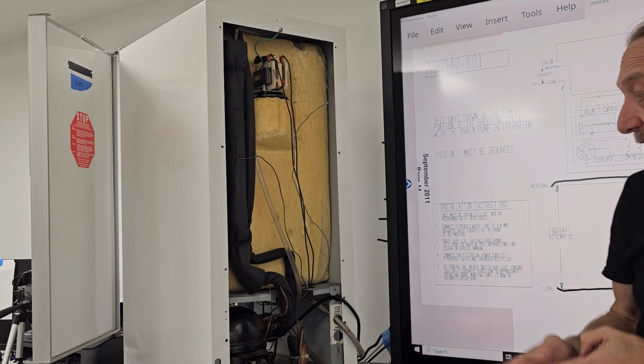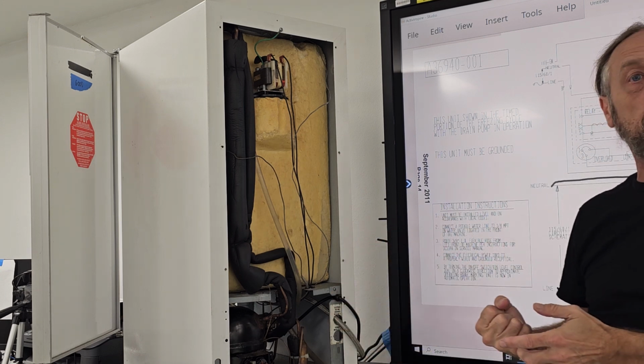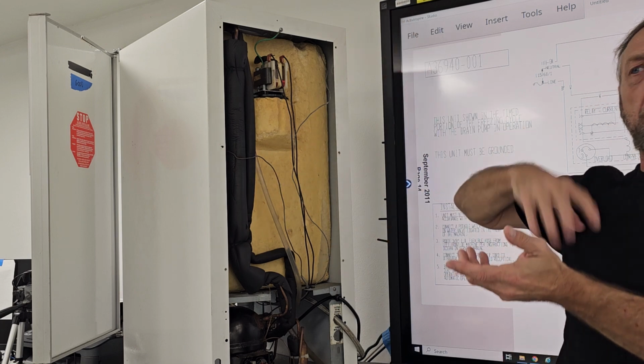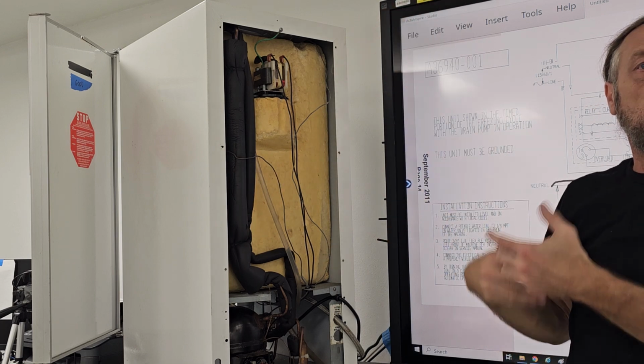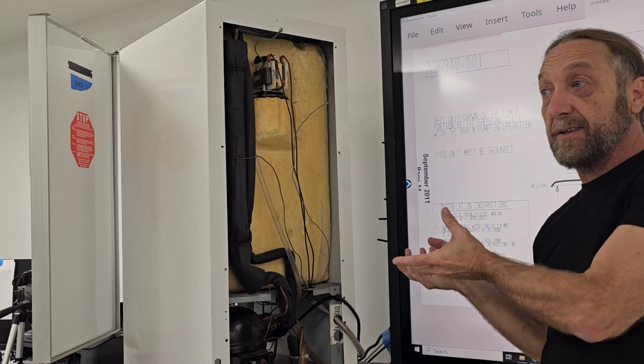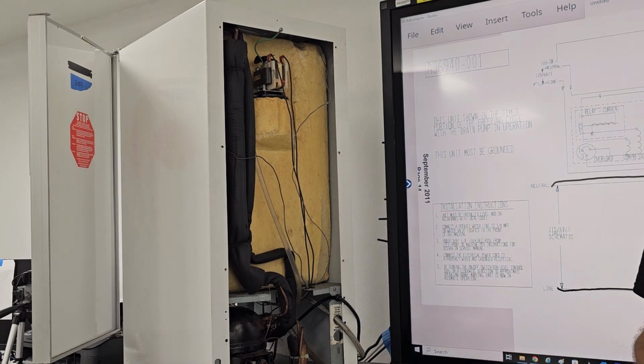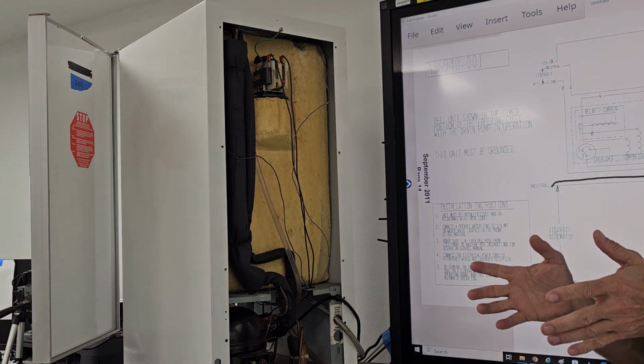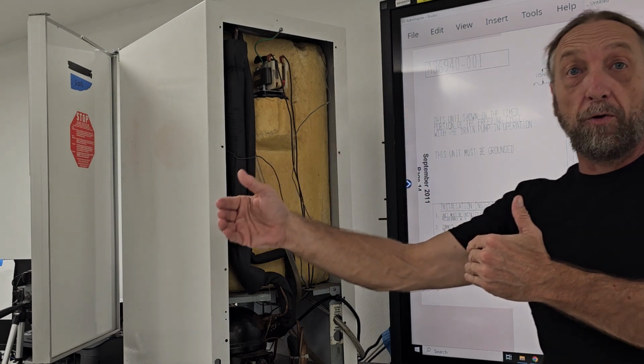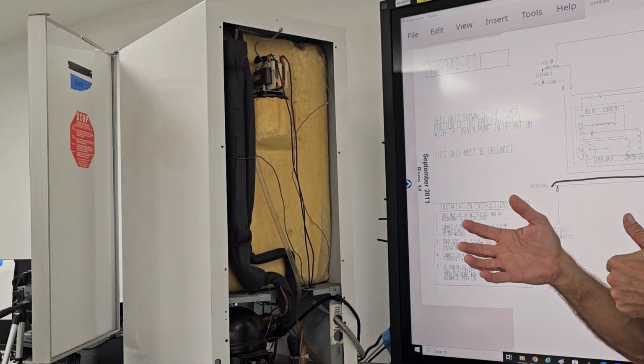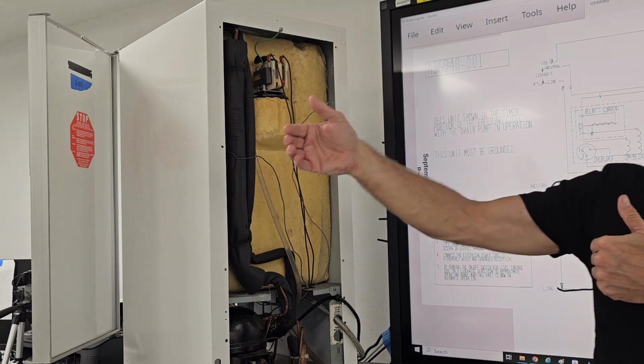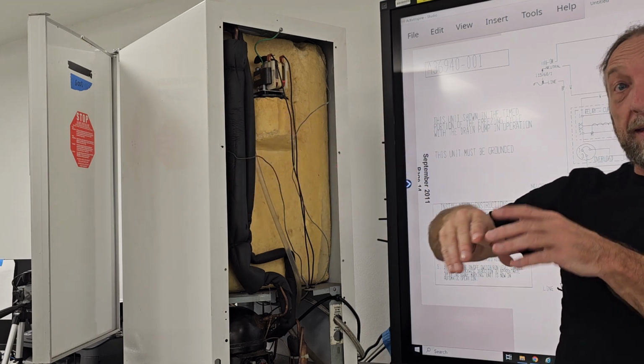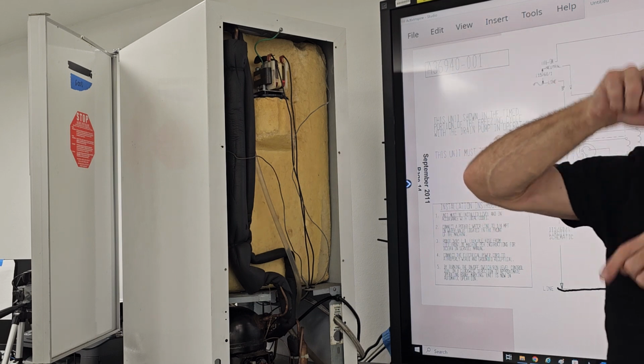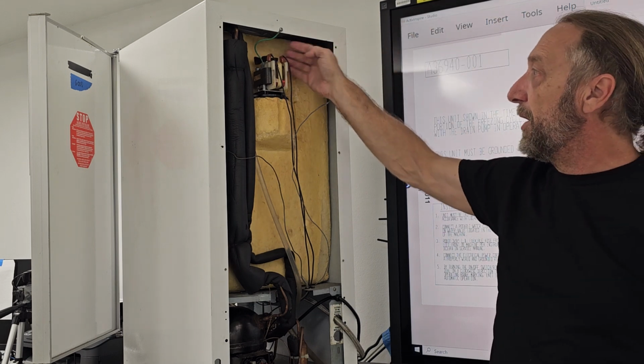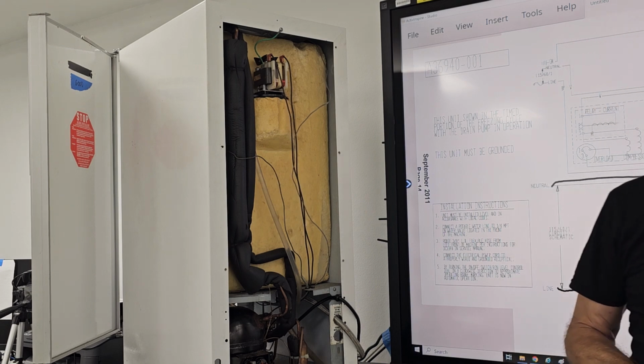Now, if the water valve is bad and not allowing enough water to come in, you could be halfway through ice production and then there's just no more water circulating. The machine doesn't have any flow device to say, hey, we're low on water, give me more water. The water is a timed fill. Based on this much water pressure, they go a little bit over in the time. So in other words, if it takes a minute and a half to fill, they'll run that water valve for like 2 minutes. And that's what that overflow pipe was for. Okay? So this is our recirculation pump here, and you have to access that through the rear of the unit.